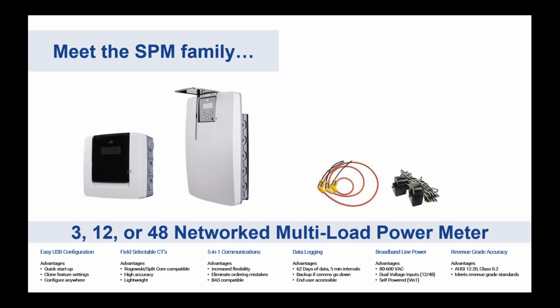To the right of those are more traditional split core CTs. Those CTs we carry in 20, 50, 100, 200, and 400 amps. And then from there, people will usually transition over to the Rogowski coils for the higher amperage range. Our split core CTs are UL 2808 listed, and they also come with a 15-foot cable length, which should meet most of the cable runs you may have in the field, but both the split core CTs and Rogowski coils can be extended in the field for longer runs.